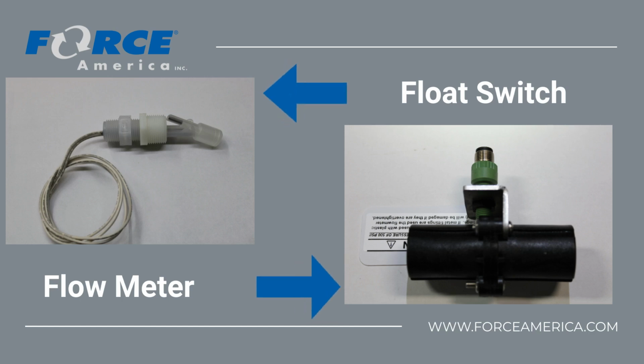The float switch sensors are installed within the tank and will activate after 10 seconds of liquid being low and automatically reset after 60 seconds of liquid being added. The delay is intended to prevent sloshing from generating false warnings. When the liquid flow meter no longer detects liquid for a period of 10 seconds, the 60-100 spreader control will also display a low liquid warning on screen, as well as a feedback error and disable the liquid system.